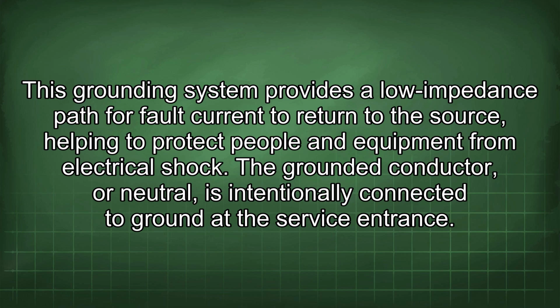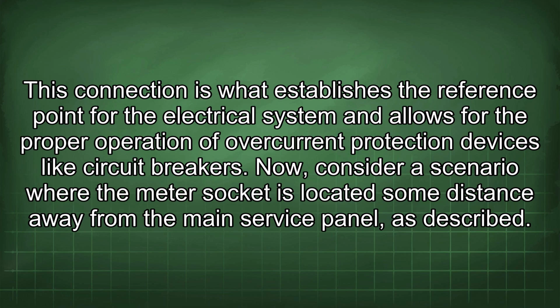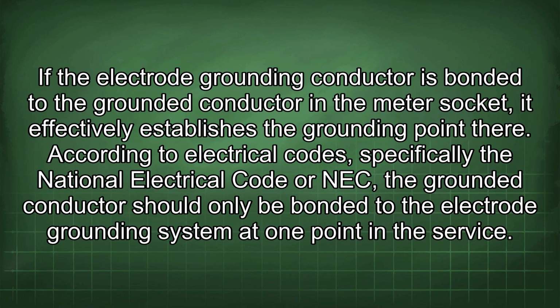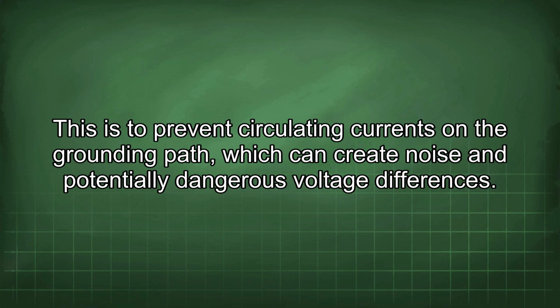The grounded conductor, or neutral, is intentionally connected to ground at the service entrance. This connection is what establishes the reference point for the electrical system and allows for the proper operation of overcurrent protection devices like circuit breakers. Now consider a scenario where the meter socket is located some distance away from the main service panel, as described. If the electrode grounding conductor is bonded to the grounded conductor in the meter socket, it effectively establishes the grounding point there. According to electrical codes, specifically the National Electrical Code or NEC, the grounded conductor should only be bonded to the electrode grounding system at one point in the service. This is to prevent circulating currents on the grounding path, which can create noise and potentially dangerous voltage differences.